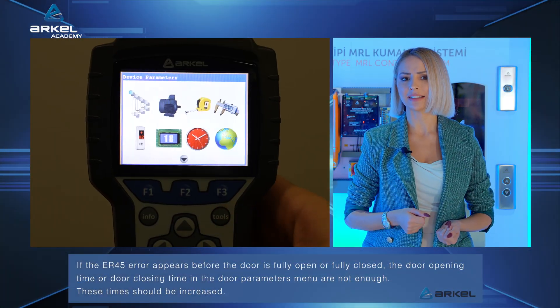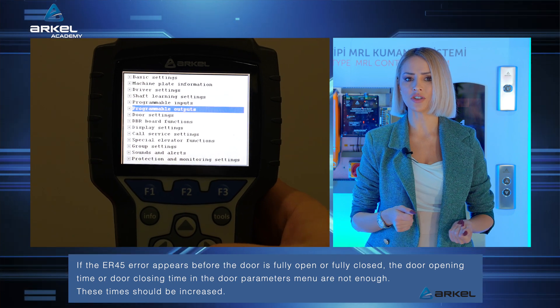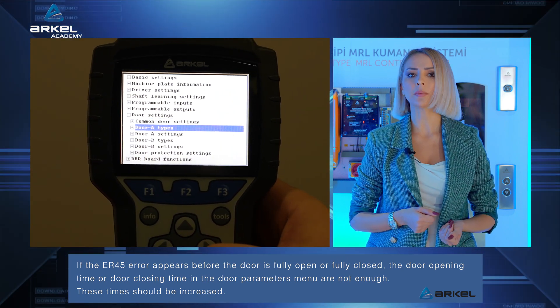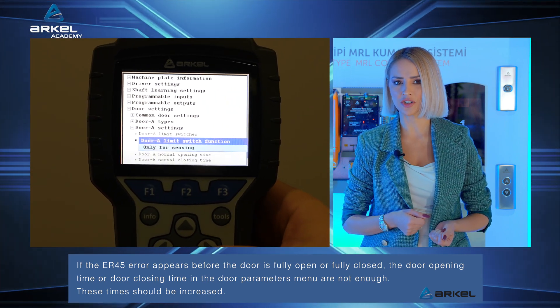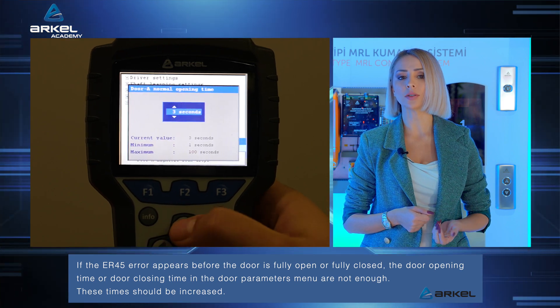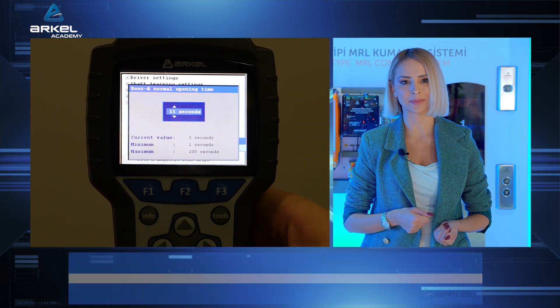If the ER45 error appears before the door is fully open or fully closed, the door opening time or door closing time in the door parameters menu are not enough. These times should be increased.